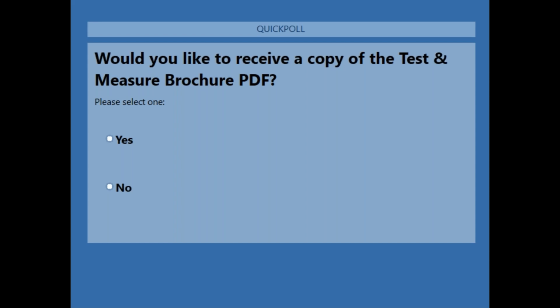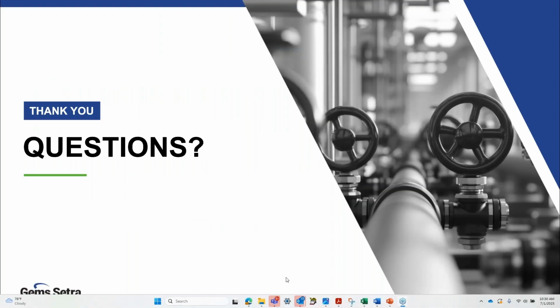All right, Matt, it looks like there's a couple questions in the chat. The first one is, what range transducer would you use for clean room positive pressure? I would select either the 201 series, any of the low pressure sensors that measure 5 to 25 inches of water column are suitable for measuring that very low pressure. We also have a portfolio of HVAC products that can also serve those very low pressure ranges for room pressure monitoring.